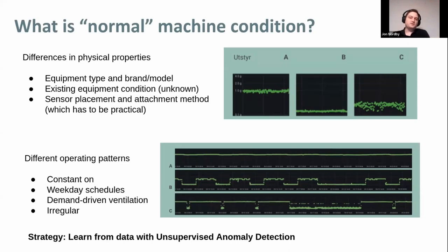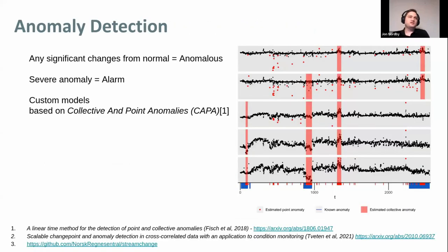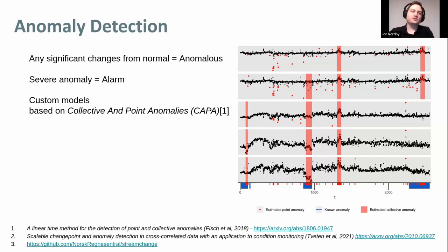To handle this complexity, we use machine learning to automatically learn the patterns of a particular device using unsupervised anomaly detection. In anomaly detection, we learn the normal pattern and any change from that is considered anomalous. If it's a severe anomaly — meaning it has a high anomaly score — and it persists for a longer period of time, typically more than one hour, then we consider this as an alarm. We have tested many approaches and are currently mostly using custom models based on the CAPA framework, which is specifically designed to handle collective anomalies — longer periods of time in an anomalous state — indicative of a machine state change or condition change.